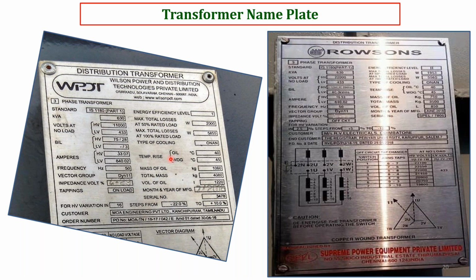the old transformer does not have these details. That's a very important point. The old transformer does not have this IS standard. Of course, they have a different IS standard value, but it's not an energy efficiency standard. More particularly, IS 1180 based transformers have a loss indication represented on the nameplate itself. Now, if you are operating the transformer at 50% loading condition, then automatically the self loss of the transformer is going to be 2 kilowatt.